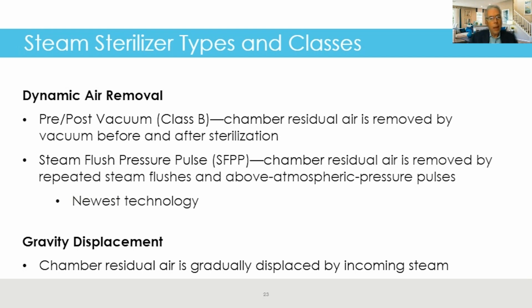Now, when it comes to autoclaves, there are really two types you're going to see on the market. I call it the older style gravity displacement and the newer style dynamic air removal. These pre-post vacuum machines, these Class B devices - in those, the autoclave chamber air is actually removed by vacuum before and after sterilization. That's why they're faster, that's why they're more efficient, and that's why you get bone dry packaging. I myself have gone to one of these for that very reason - I get bone dry packaging.